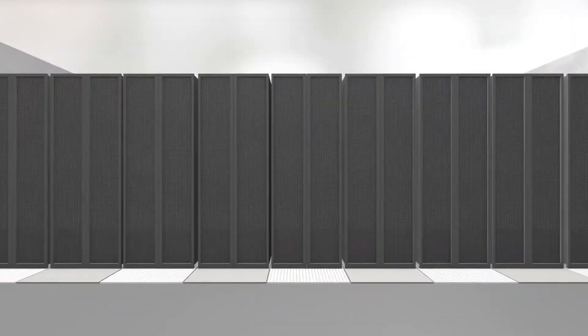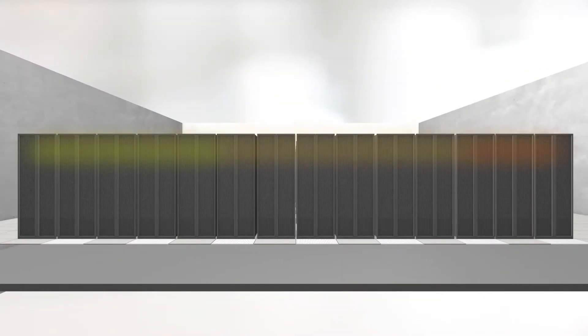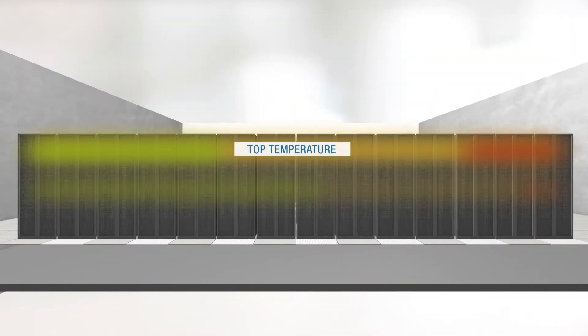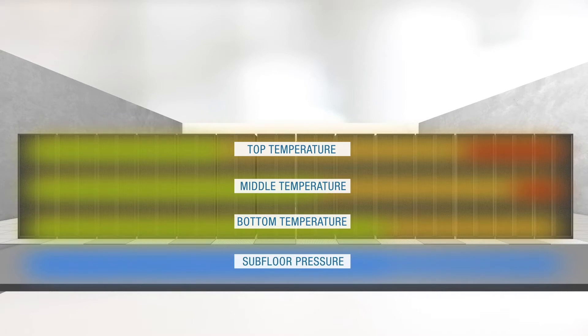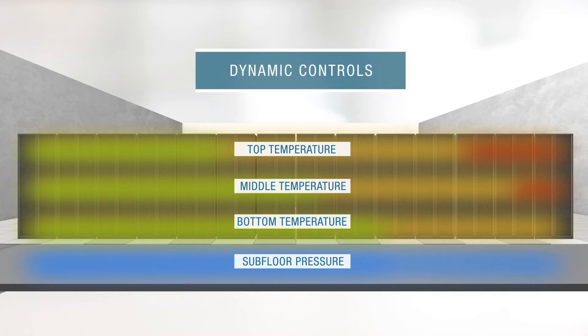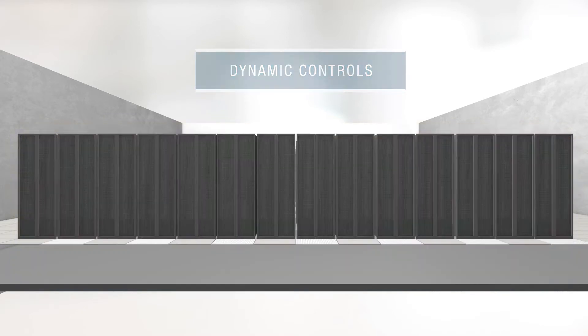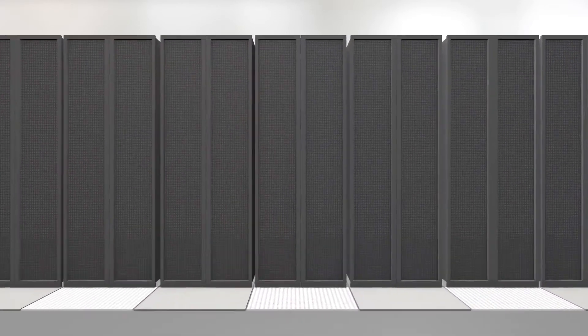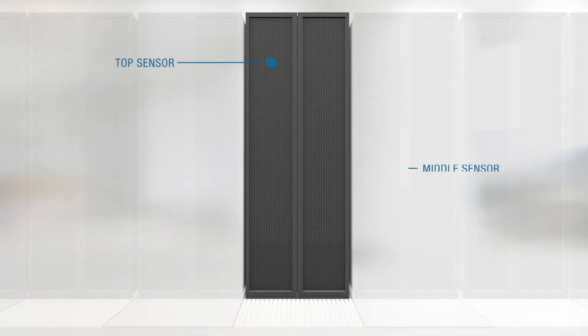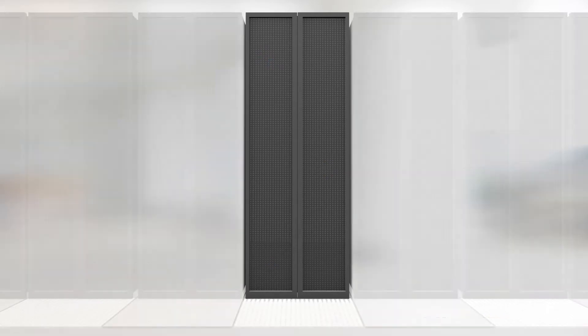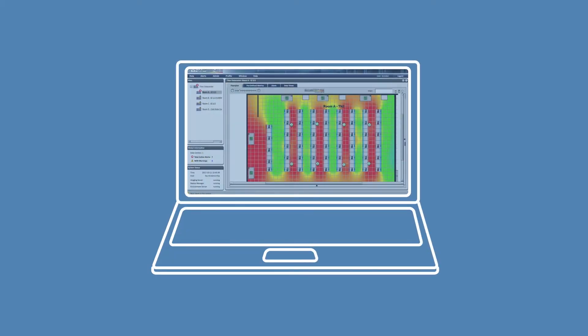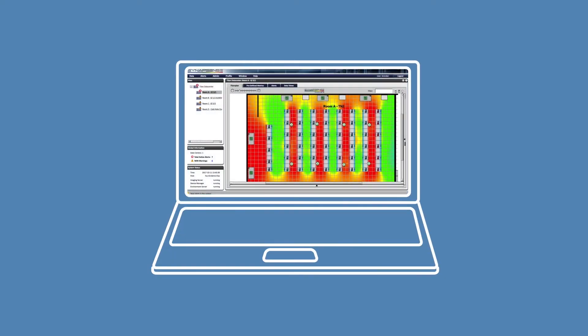Active control was the logical solution for these issues. Active control enables data center operators to control cooling resources dynamically to better align capacity and demand. It acts on data received from Synapsense wireless sensors, which measure server inlet temperatures and subfloor pressure differentials to manage cooling unit return temperature set points and variable fan speeds.